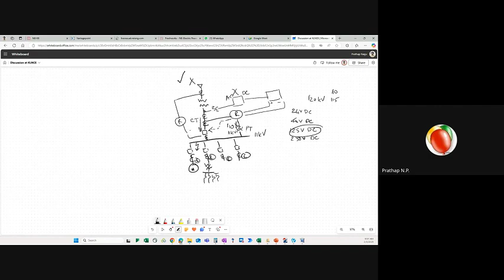The CT is there for overcurrent protection, so every feeder has its own relay, that's 4 control cables per feeder. On top of that, if you have differential protection, that's a separate connection, 3 and 3 is 6 relays. And if you have bus differential, that's even more, it goes across all the feeders. When you start adding like this, even in a very simple substation like this one, it adds up.